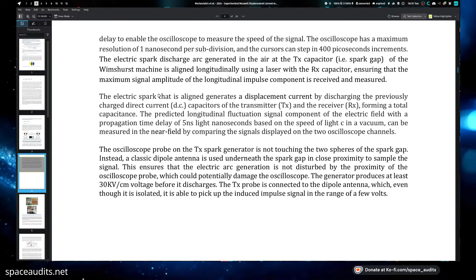The oscilloscope probes on the transmitter spark generator are not touching the two spheres of the spark gap. Instead, a classic dipole antenna is used underneath the spark gap in close proximity to sample the signals. This ensures that the electric arc generation is not disturbed by the proximity of the oscilloscope probe, which could potentially damage the oscilloscope. The generator produces at least 30 kilovolts per centimeter of voltage before it discharges. The transmitter probe is connected to the dipole antenna, which, even though it is isolated, is able to pick up the induced impulse signal in the range of a few volts.